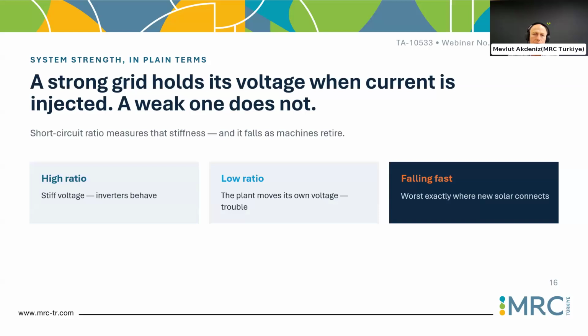As I mentioned, strong grid and keeping the voltage in an operational value is the issue. So what does strong grid mean here? It is strong in terms of voltage capability. The first item is the short circuit ratio. If I have a high short circuit ratio, it means that I have many synchronous generators nearby. So if any fault occurs in the region, the voltage at the faulted bus bar is depressed, but the surrounding or remaining bus bars' voltage would not be practically zero. I mean, the voltage is not depressed too much if the grid is strong at that point.